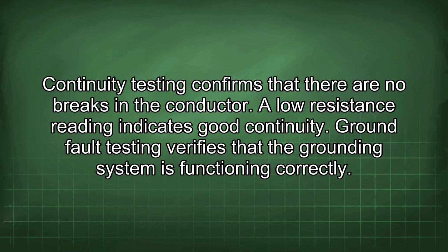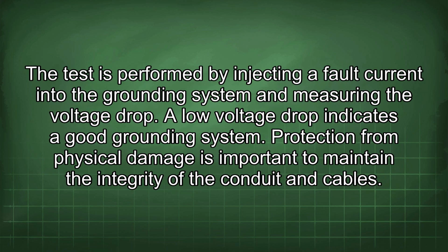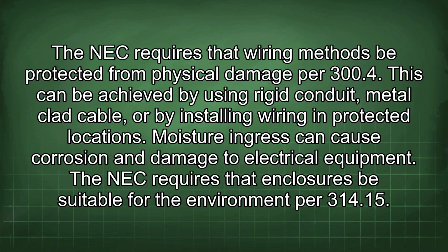Ground fault testing verifies that the grounding system is functioning correctly. The test is performed by injecting a fault current into the grounding system and measuring the voltage drop. A low voltage drop indicates a good grounding system. Protection from physical damage is important to maintain the integrity of the conduit and cables. The NEC requires that wiring methods be protected from physical damage per 300.4. This can be achieved by using rigid conduit, metal-clad cable, or by installing wiring in protected locations.